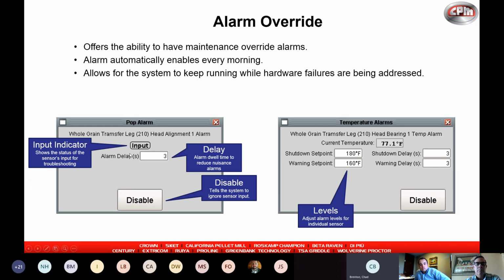The indication here gives you the status of that input. So while they're working on it, the guy in the control room can tell, hey, it's working, or it's not working, giving feedback without needing an electrician in the panel and another out working on the sensor. The same goes for analog.